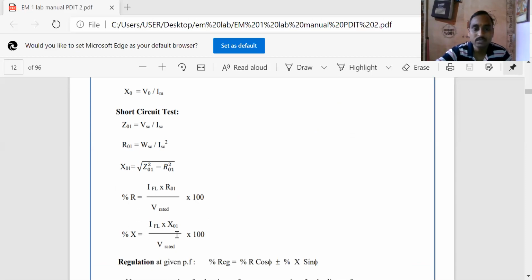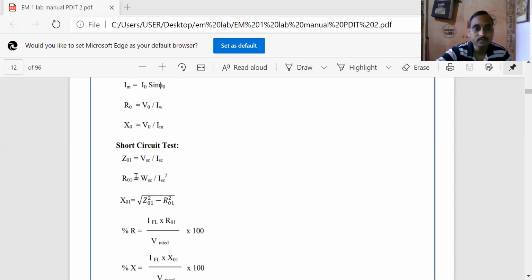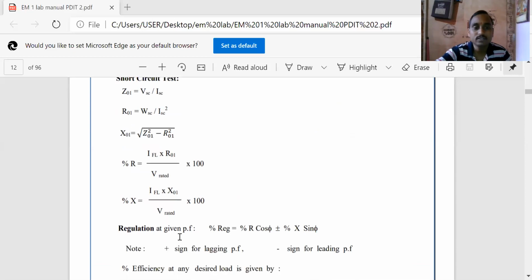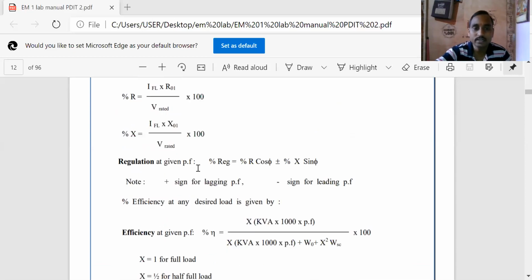Similarly, percentage X can be calculated using X01. After this, the regulation at a given power factor, the percentage regulation, is given by percentage R cos phi plus or minus percentage X sin phi.